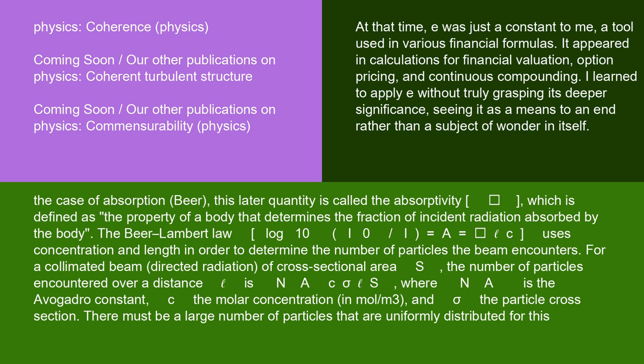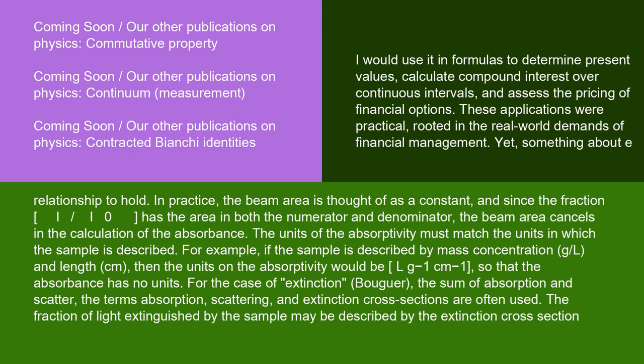There must be a large number of particles uniformly distributed for this relationship to hold. In practice, the beam area is thought of as a constant, and since the fraction I/I₀ has the area in both numerator and denominator, the beam area cancels in the calculation of the absorbance. The units of the absorptivity must match the units in which the sample is described. For example, if the sample is described by mass concentration g/L and length cm, then the units on the absorptivity would be L g⁻¹ cm⁻¹, so that the absorbance has no units.